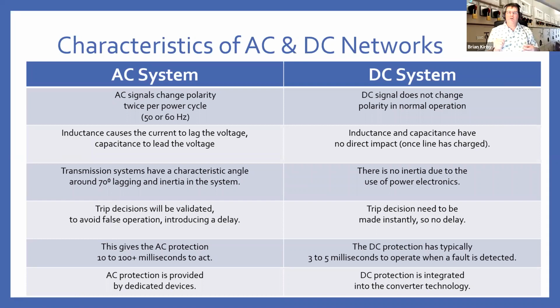Trip decisions on AC systems will be validated, because what you don't want is a false operation to disconnect your customers if you can avoid it, because there are strict penalties associated with that. So therefore, you can delay your trip decision and validate your choice before you turn the energy off. However, on a DC system, you don't have that luxury, because of the way faults propagate, you need to instantly make a decision.